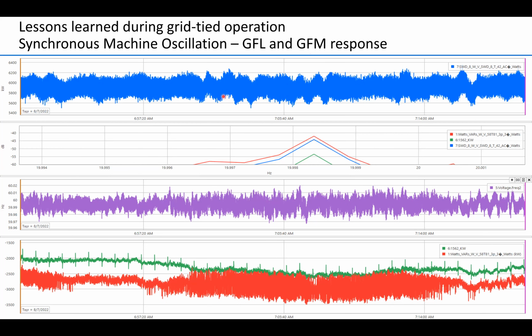oscillations to the grid. Namely, this is one of our diesel generators here, and this is its real power output. And we've seen when this unit's on, it's actually pushing out subsynchronous frequencies in the 3, the 6, the 10, and 20 hertz frequencies onto the grid. And you can really tell that because when you see one of these synchronous generations online, our 60 hertz frequency on the island gets really noisy. It looks just like this. And it's like, well, how come it's not closer to 60 hertz? Well, it's because all those subsynchronous oscillation frequencies are actually causing this noise here.